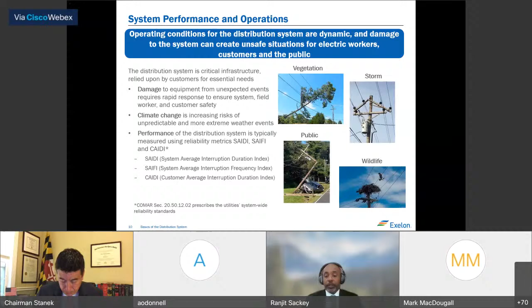So what happens when outage events occur? The distribution system has devices that sense faults and open when they do, de-energizing downstream lines to protect equipment and the public. These are protective devices, such as relays and breakers in substations, circuit reclosers at various points in the feeder main stems, and fuses on branches. These devices are placed strategically to minimize the impact of events to as few customers as practical.